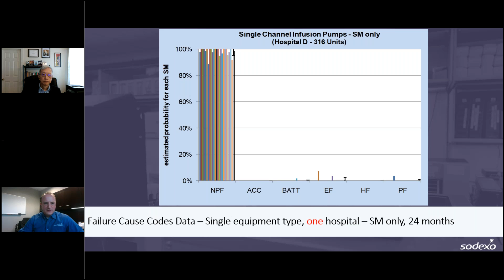So this is, again, a single equipment type for one hospital, corrective maintenance for 24 months. Cannot duplicate, which is technically a legacy term for no problem found. At the end of 24 months, we captured the average and standard deviations. While yes, there is variability, they all do line up within that standard deviation window to help find a common fault. So service-induced and preventable and predictable failures are practically non-existent. Those are the 2 on the right-hand side of the screen.